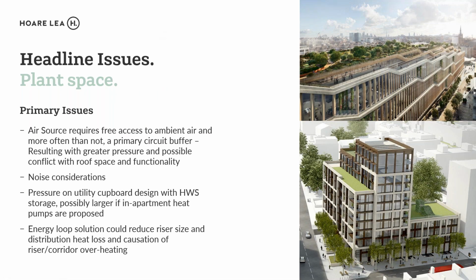With air source heat pumps in particular, we're now having discussions rather than just chillers, but also the heat source that used to be in the basement with flues going up through the roof. We're now looking at the likes of chillers on the roof, and that's impacting on the roofscape, because we're finding that most residential developments have the pressure of amenity space, and there's a lot of greening of roofs. So there's a great discussion with the architect for the early doors with regards to roof space allocation. And alongside that goes noise, because the evaporator fans on the heat pumps generate noise that needs to be controlled, particularly in residential, and how that amenity space can work alongside plant space.